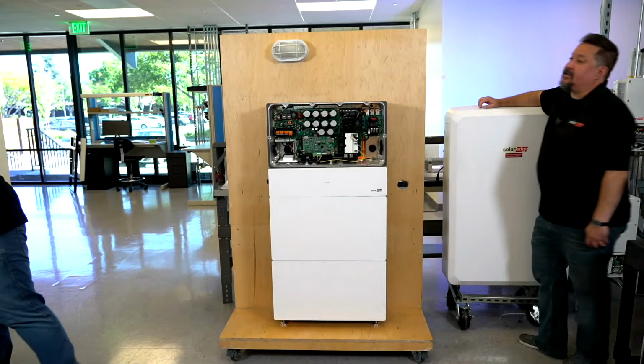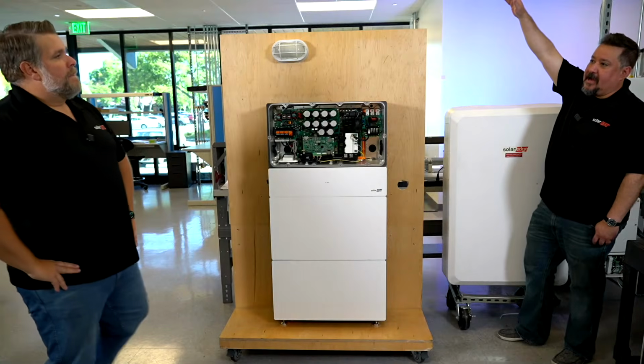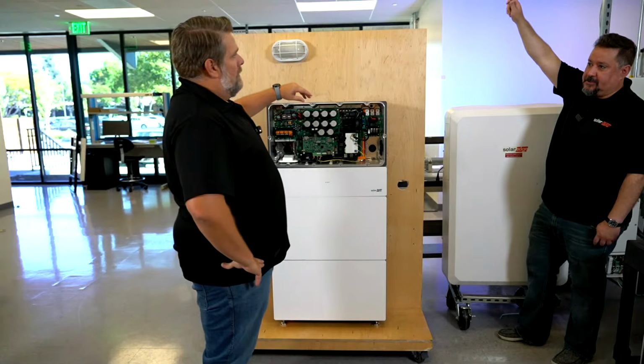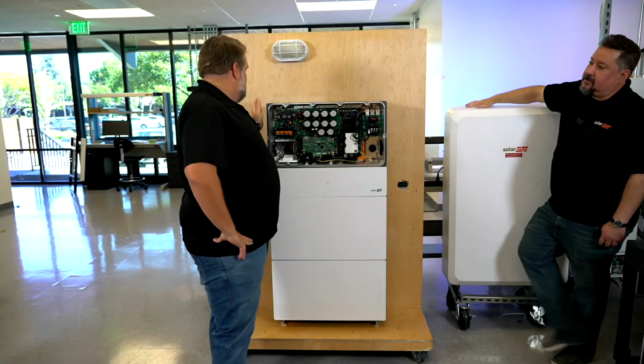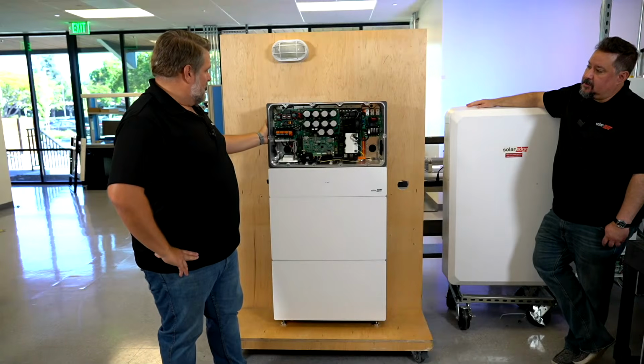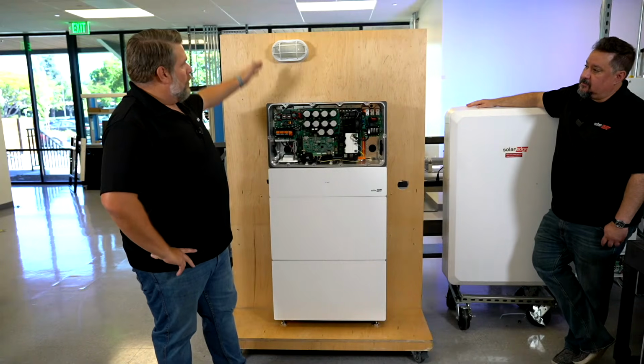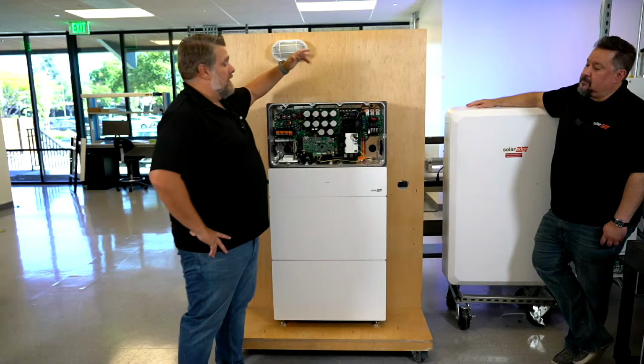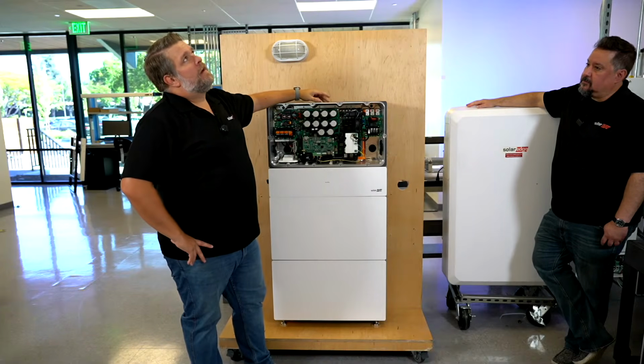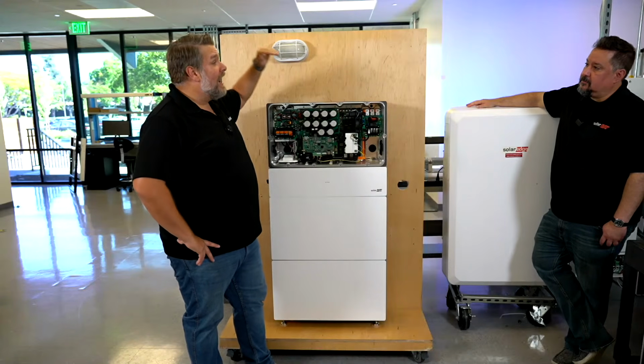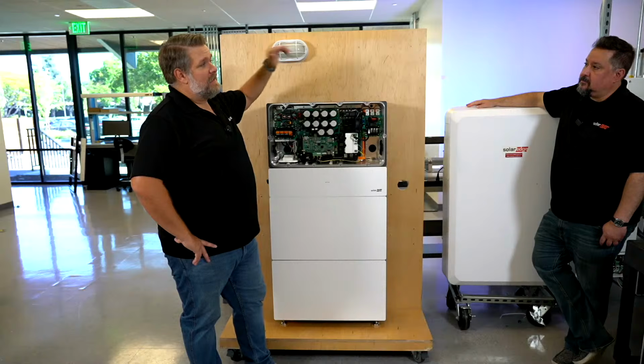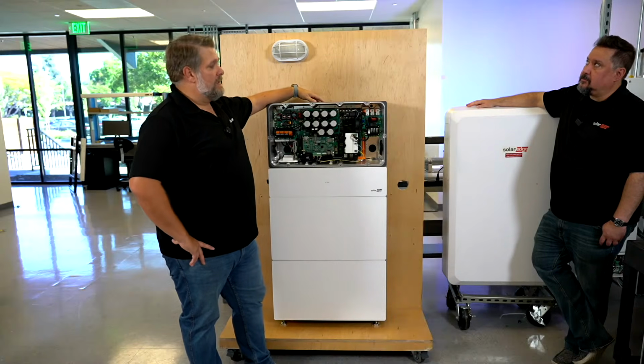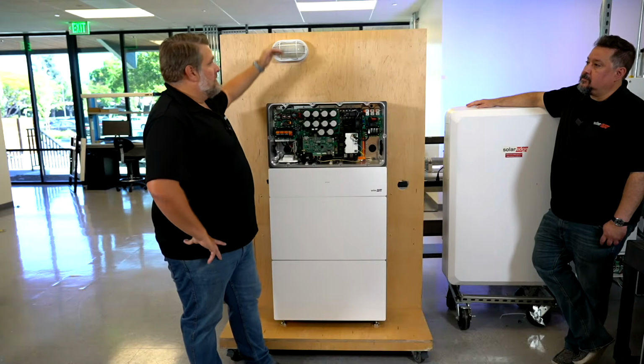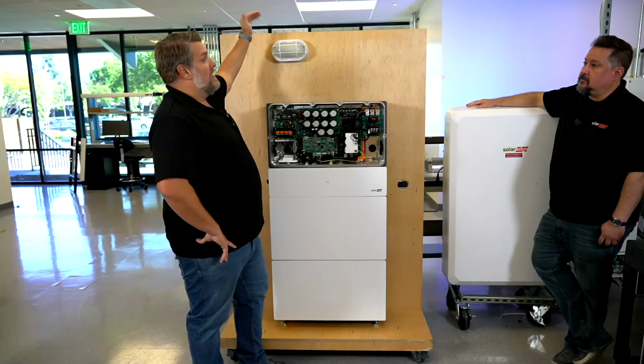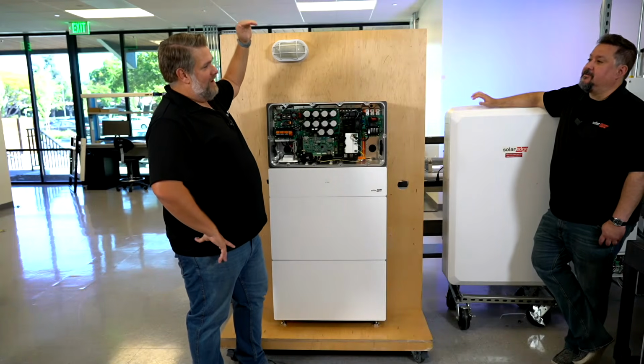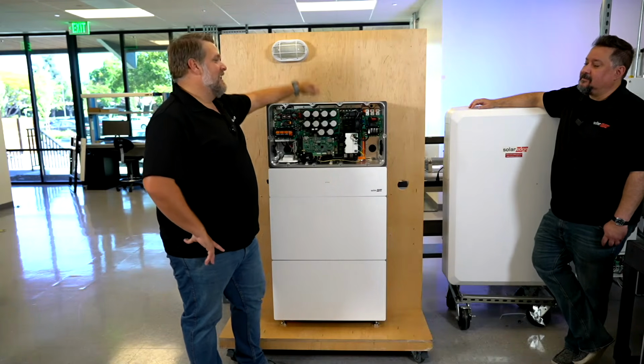That's a good point. With the 4 stack, can you still reach code compliance? There's a DC disconnect switch right here on the left-hand side. With the 4 stack, the NEC code says you cannot have a disconnect switch higher than 6 feet 7 inches, so 79 inches. With the 4 stack, you're 2 inches underneath that, at 77 inches.